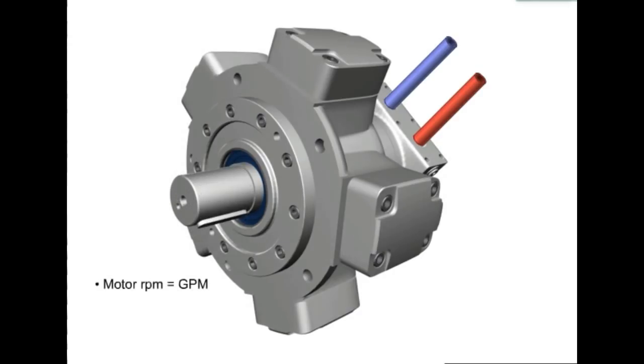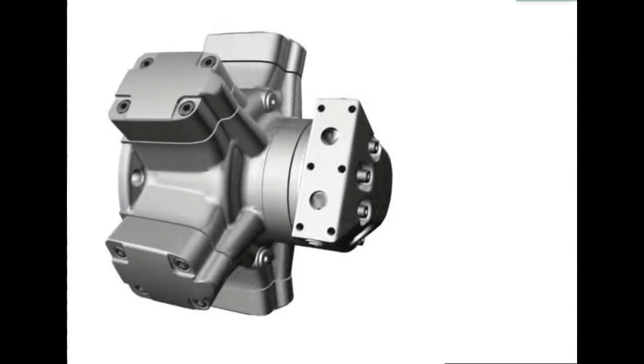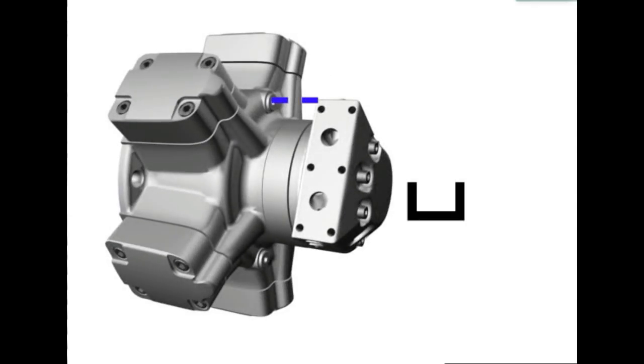Output speed of the fixed displacement radial piston motor is proportional to the input flow. Drive torque is proportional to the difference in pressure between the motor inlet and the outlet. Any internal leakage passes into the area between the rotating group and the housing. This leakage is directed from the case drain port directly back to the reservoir.